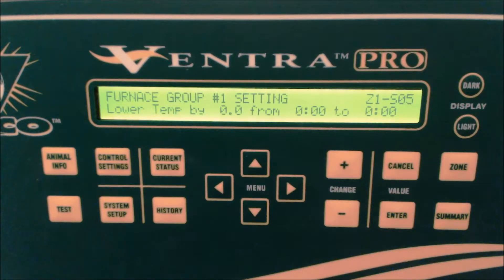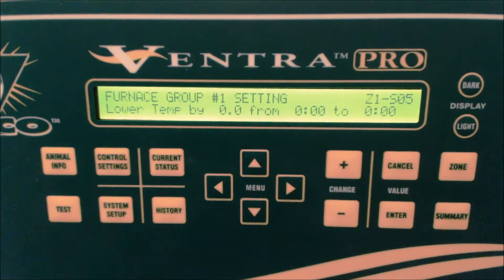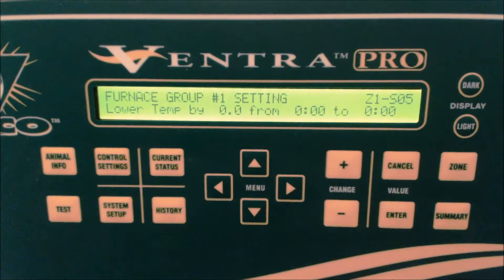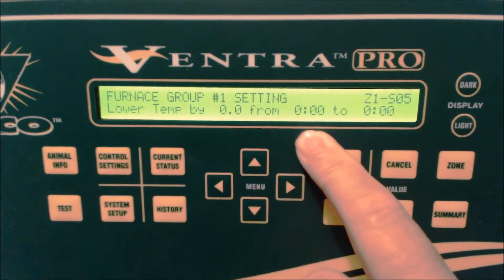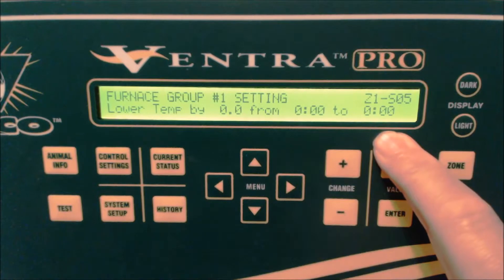The first setting on this screen is the number of degrees you wish to drop the on/off temperature of the heating device by. The range is 0 degrees, which disables the feature, to 15 degrees. This is a positive number which tells the controller to drop the heating settings by this number of degrees when the feature takes effect. The second setting is the time of day that you wish the feature to enable. The third setting is when you want the feature to disable.